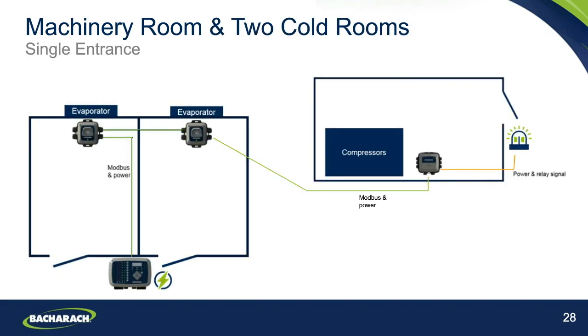Add on the machinery room to a cold room setup, and of course we again need to have the gas detection within the machinery room as well as those cold rooms. But we can see here it's possible to again centralize that whole system with indication within one controller by running both power and communication lines back to that, simplifying the installation such that there is only one primary power connection that needs to go in, but enabling the gas detection that you need and enabling all of the power and relay signaling that you need outside of each entrance within the machinery rooms and cold rooms.